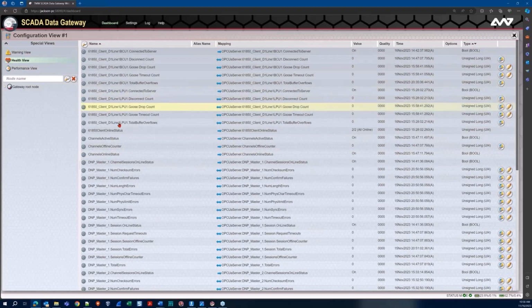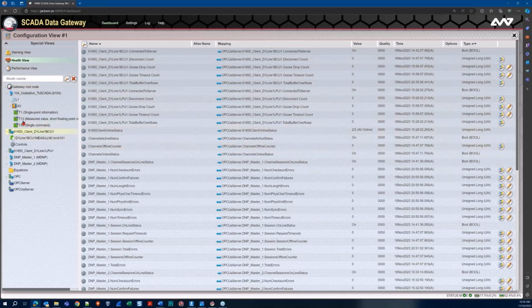So for example, let's just say channel online status or maybe offline counter. Right now I have 0 devices offline. If this was 1, for example, indicating that I did have a device offline, it would be available in my warnings. Now I also might want to map this value up to my 104 side, just to give some diagnostic information to let the SCADA side know how the gateway is performing. Easy to do - I just take that counter and drag it over to, for example, the measured values.